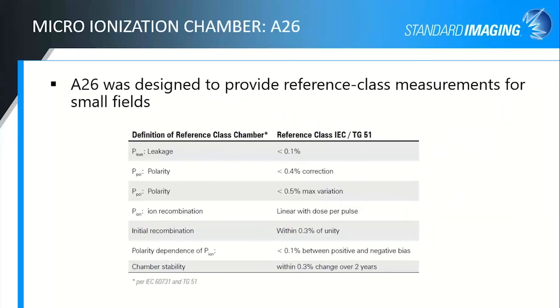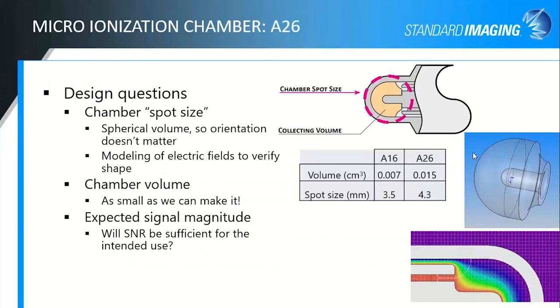So it was designed to provide reference class measurements for your small fields, to meet the conditions of what a reference class chamber is. When we were designing it, we had to ask ourselves questions like, what spot size can we get to? Does it matter if it's spherical, or could it be elongated? And we really did settle on the spherical being the best geometry, so that your orientation doesn't matter and your volume averaging is uniform no matter which direction you're scanning. We modeled the electric fields to make sure that we knew the volume precisely and we knew the shape of that collection volume.